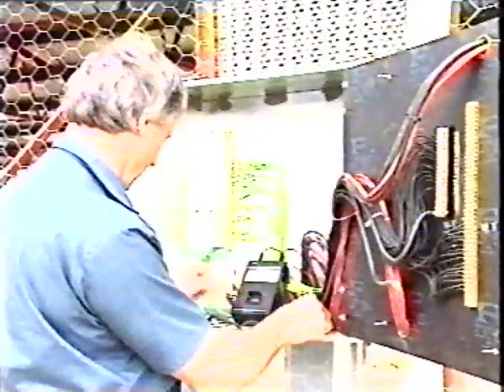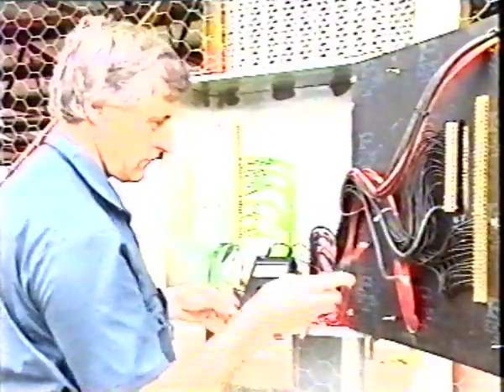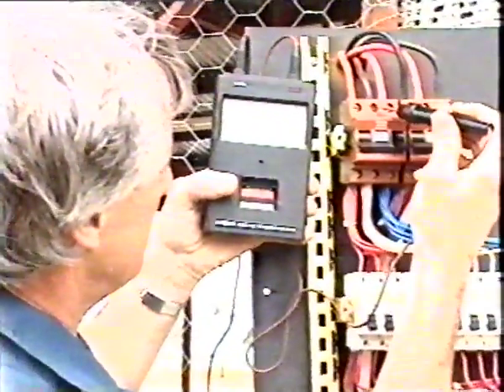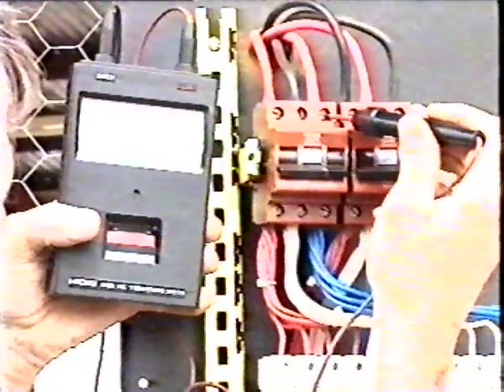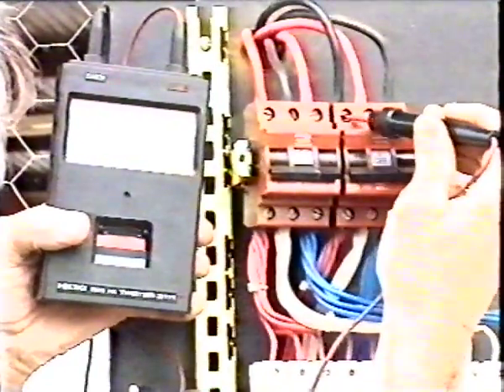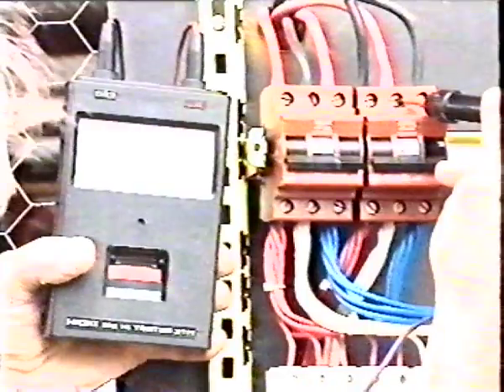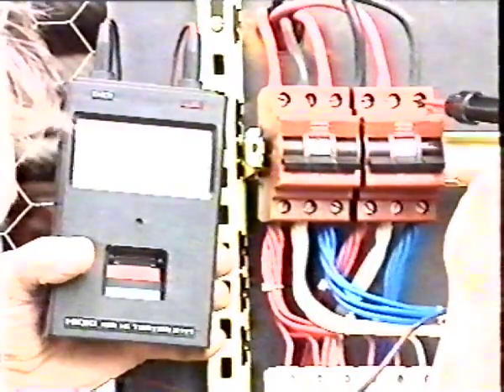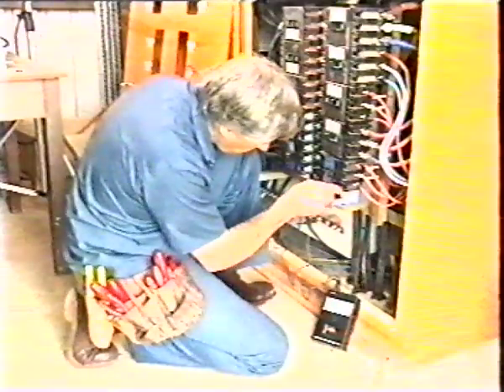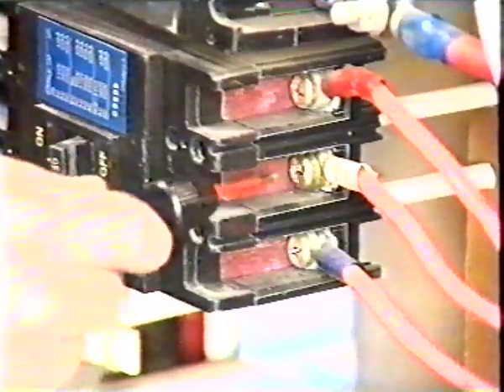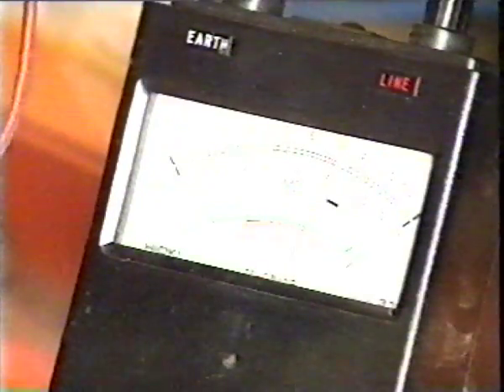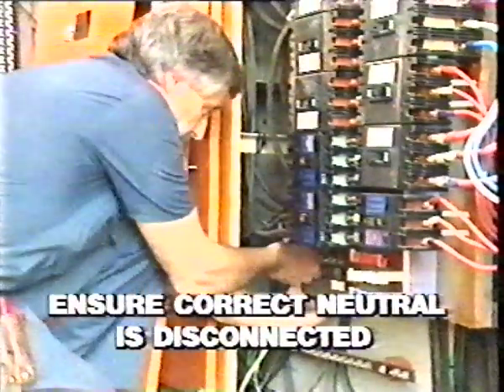This removes any connection between the neutral conductor and any outgoing circuit and earth which would confuse testing. Connect one ohm meter lead to the earthing conductor and the other ohm meter lead in turn to the neutral and active conductors. Neutral to earth should indicate a short circuit and active to earth should indicate an open circuit. Test the insulation resistance of the submain active conductor or conductors at both the distribution board and supply switchboard. While this test may have been performed during testing of the supply switchboard, a high resistance measurement at both switchboards would establish that the conductor is not connected to earth and is therefore not a neutral conductor.